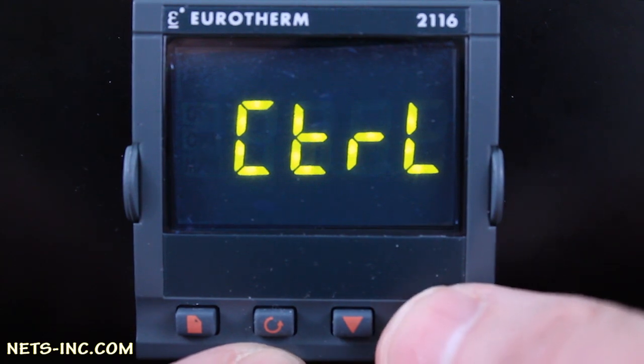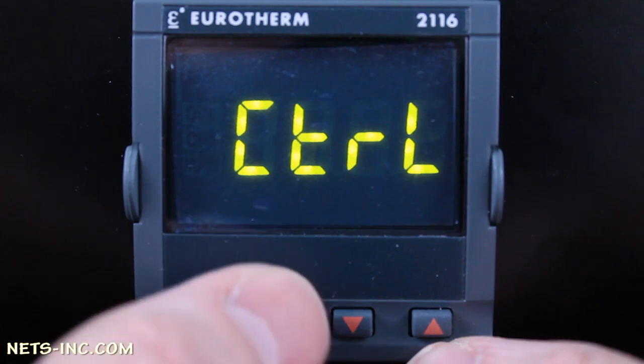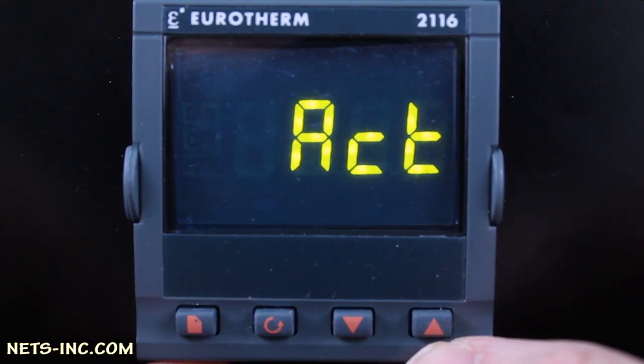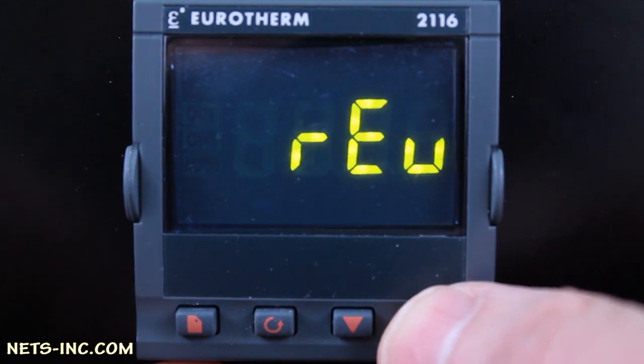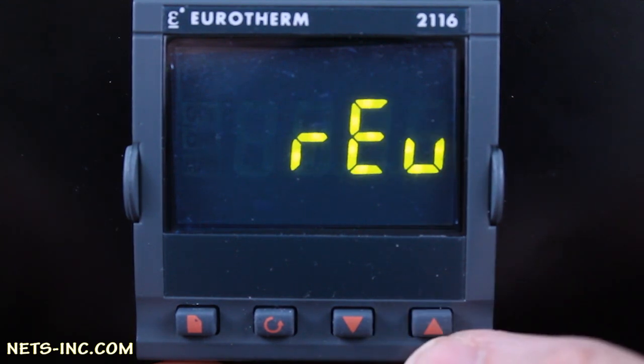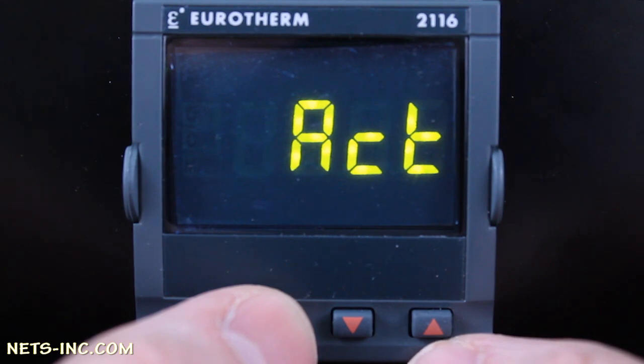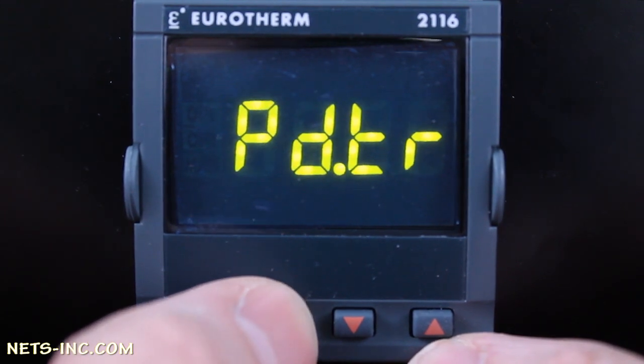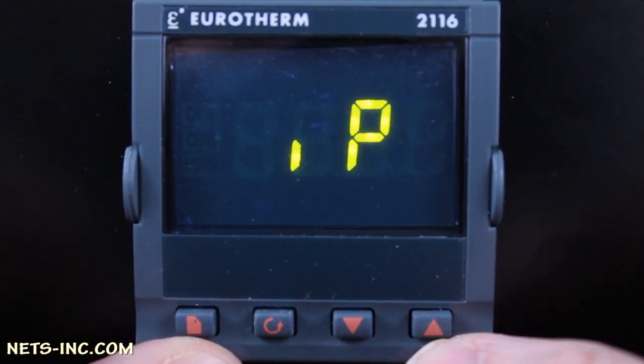Pressing the Up Arrow continually shows the other options available besides PID. Press Scroll one more time and ACT is displayed — this is the PID output action. For this type of control, reverse action is the chosen method. Press the Up Arrow to confirm it is set for REV, or reverse. Press the Scroll button until INST is displayed again.